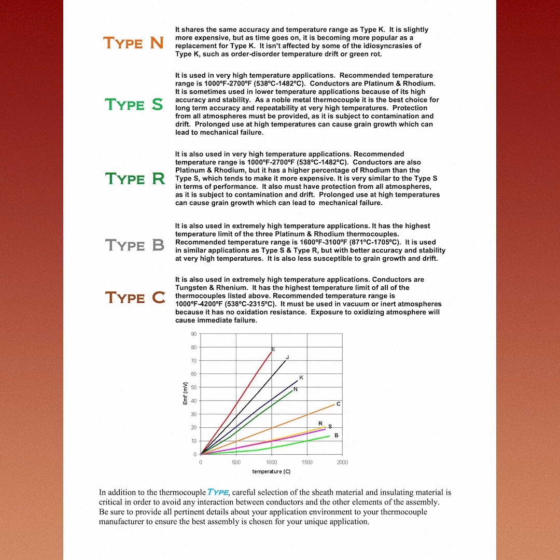Type C is also used in extremely high temperature applications. Conductors are tungsten and rhenium. It has the highest temperature limit of all of the thermocouples listed above. Recommended temperature range is 1000 to 4200 degrees F or 538 to 2315 degrees C. It must be used in vacuum or inert atmospheres because it has no oxidation resistance. Exposure to oxidizing atmosphere will cause immediate failure.